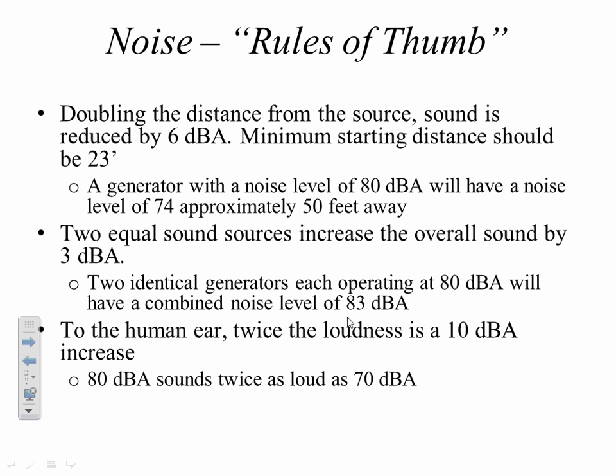A few rules of thumb for noise. Doubling the distance from the source, the sound is reduced by 6 dBA. So a generator running at 80 dBA will have a noise level of 74 approximately 50 feet away, if we started at 23 feet, approximately. Two equal sound sources will increase the overall sound by only 3 dBA. So two 80s makes 83. And to the human ear, twice the loudness is a 10 dB increase.